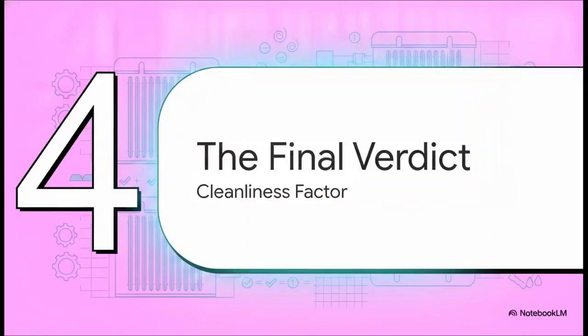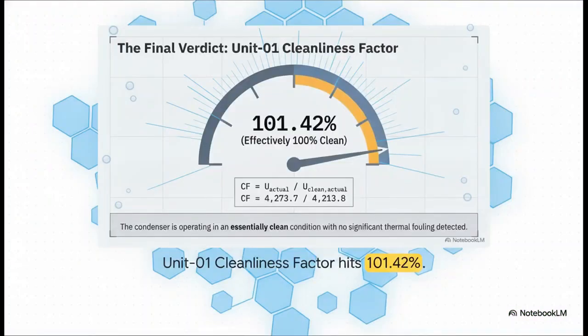All right, the math pipeline is complete. All the corrections have been applied. Time for section 4, the final verdict. Drum roll, please. By dividing our actual heat transfer coefficient by the flow-corrected expected coefficient, we get a final cleanliness factor of 101.42%. Seriously, this condenser is operating in an essentially spotless condition. We've detected absolutely zero significant thermal fouling. The tubes are clear, the heat is transferring perfectly, and the unit is running at absolute peak thermal efficiency.